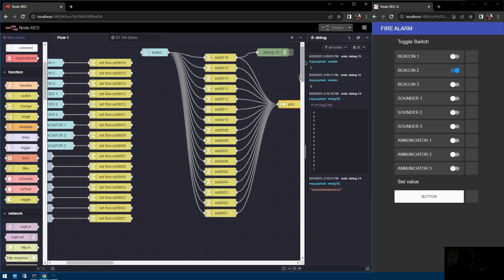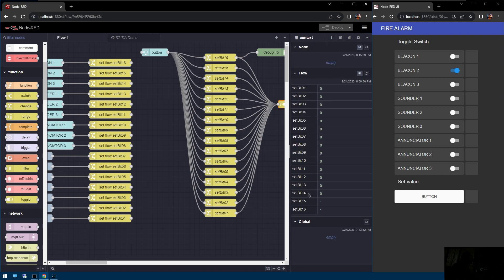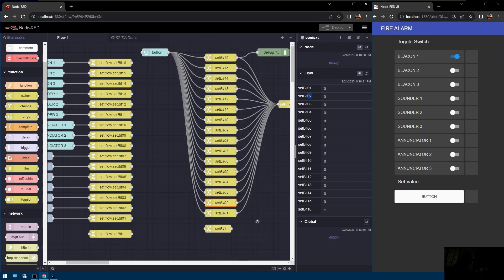You also need to pay attention to the context data sequence value. The sequence sent into the join node is ordered as 01, 02, 03 — I write it that way so values don't get interleaved. Without this, if you set bit 1, its value could be intercepted between bits 9 and 10, and bit 2 might jump after bit 16. So make sure you write the sequence like 01, 02, etc., to keep ordering correct.